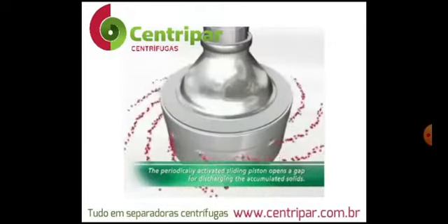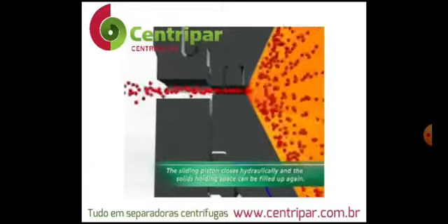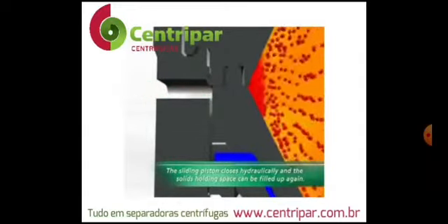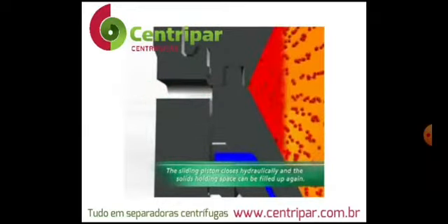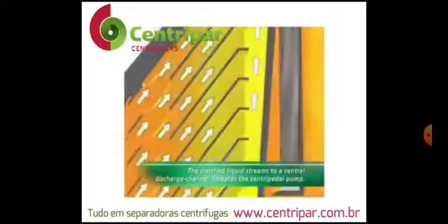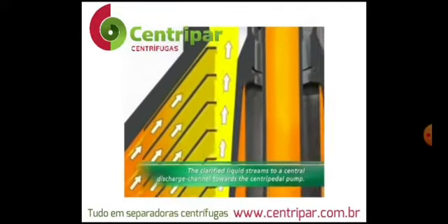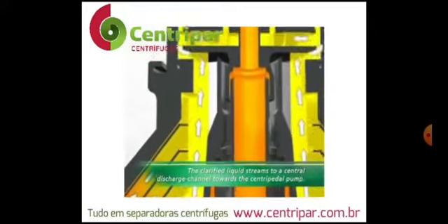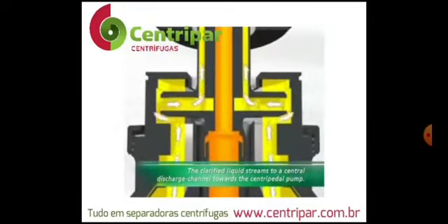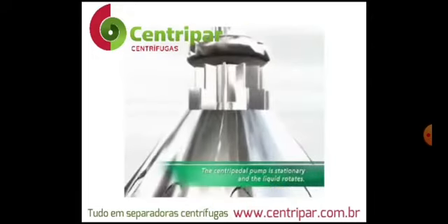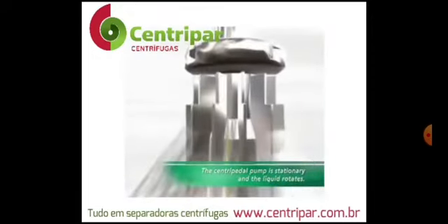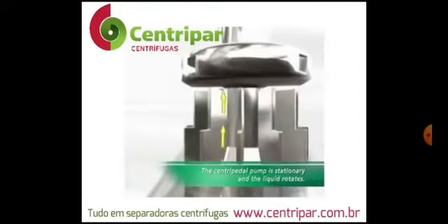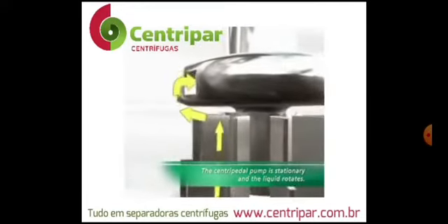Very interesting video. This is how the solids are getting, yes, there again it is closed after the discharge of solids. This is the movement of clear liquid, which is shown in yellow color. From the center the slurry is fed in, and from the outside pipes the clear liquid is coming out of the centrifuge.